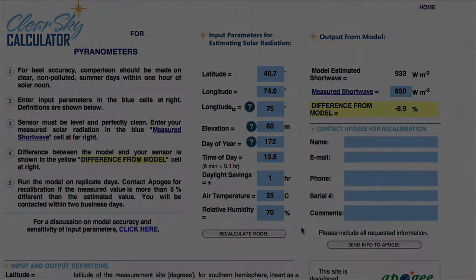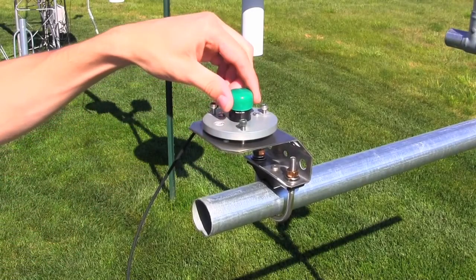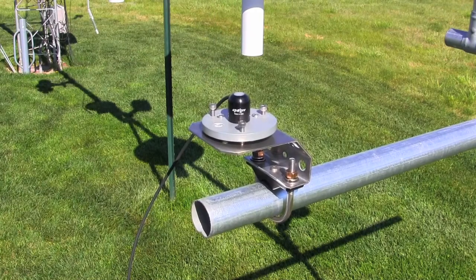That's about all there is to mounting and maintaining your pyranometer, however here are a few more tips and troubleshooting issues you might find useful. One of the simplest problems we see is people failing to remove the green protective cap from the pyranometer. The green cap is designed for protection of the lens when transporting or storing your pyranometer, but needs to be removed when you are taking readings.